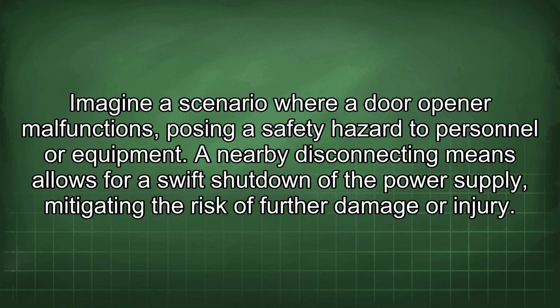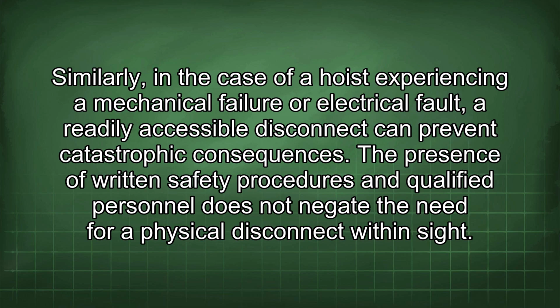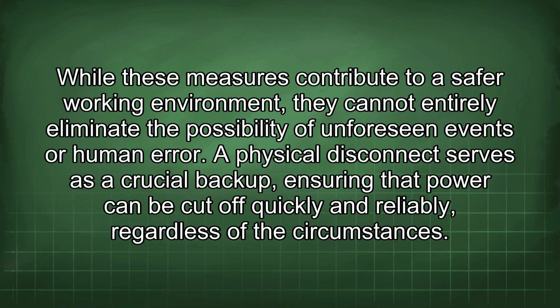Imagine a scenario where a door opener malfunctions, posing a safety hazard to personnel or equipment. A nearby disconnecting means allows for a swift shutdown of the power supply, mitigating the risk of further damage or injury. Similarly, in the case of a hoist experiencing a mechanical failure or electrical fault, a readily accessible disconnect can prevent catastrophic consequences. The presence of written safety procedures and qualified personnel does not negate the need for a physical disconnect within sight. While these measures contribute to a safer working environment, they cannot entirely eliminate the possibility of unforeseen events or human error. A physical disconnect serves as a crucial backup, ensuring that power can be cut off quickly and reliably, regardless of the circumstances.